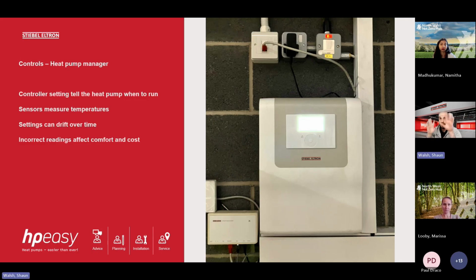It's important as well that we check, say, the sensor placements. So our weather compensation sensor, which sits outside on the wall, if that is in the incorrect place, or it's moved, or it's fallen down, or there's water ingress into the sensor, it could potentially trick the heat pump into thinking it's maybe warmer than it is or colder than it is outside. And if that happens, it means the machine is trying to compensate for that by either running to higher temperatures or running at really low temperatures, thinking it's a lot warmer outside than it actually is.